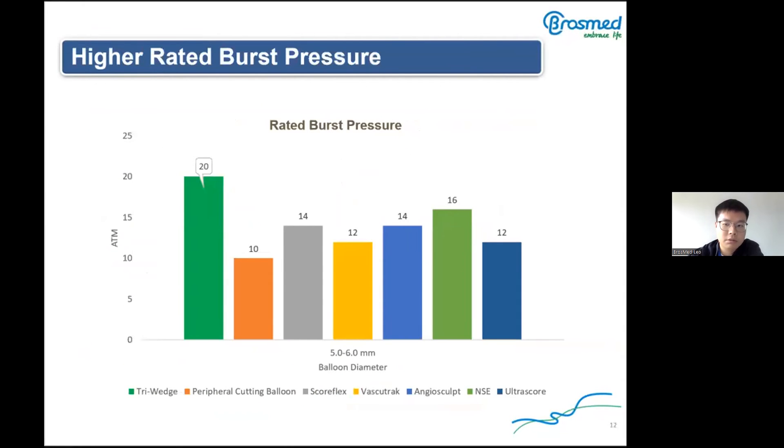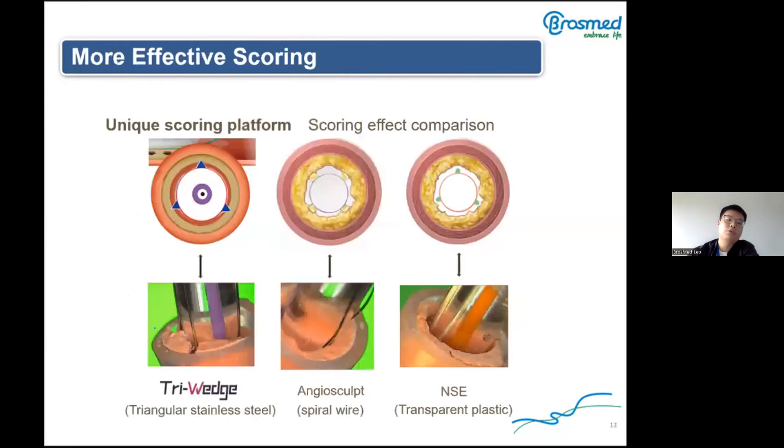Now let's look at the specific performance. The rated burst pressure of the Tri-Wedge is higher than similar competing products. It can be used up to 20 ATM, which improves safety during operation. We used the Tri-Wedge and similar competing products to expand simulated calcified lesions, and the Tri-Wedge can crack the simulated calcified lesion at the same pressure, benefiting from its unique triangular cross-section scoring elements, which are more effective for stress focusing.